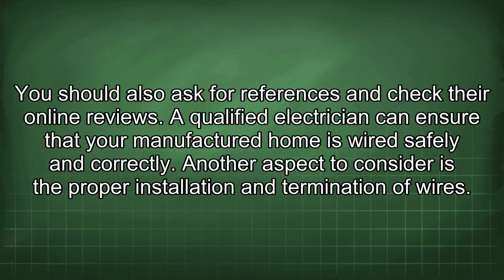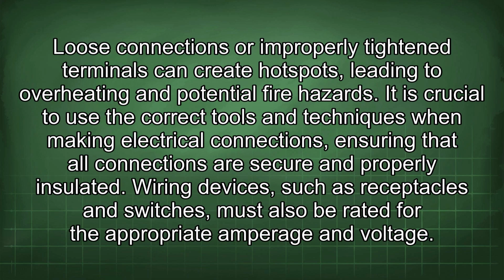Another aspect to consider is the proper installation and termination of wires. Loose connections or improperly tightened terminals can create hotspots, leading to overheating and potential fire hazards. It is crucial to use the correct tools and techniques when making electrical connections, ensuring that all connections are secure and properly insulated. Wiring devices, such as receptacles and switches, must also be rated for the appropriate amperage and voltage.